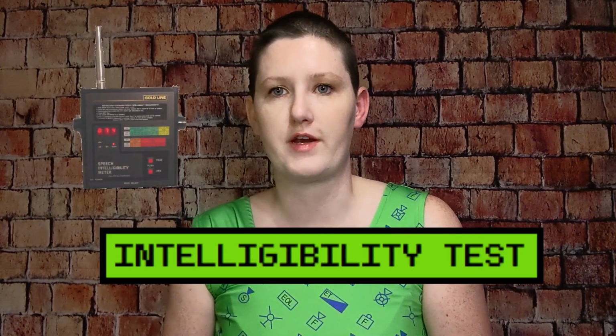Speakers are just like any other speaker, but they have more strict requirements on functionality and intelligibility. Often jurisdictions will require an intelligibility test, during which a tone-generating device is connected to the input of the EVAC panel or mass notification panel. The inspector will walk around the building with a device with a microphone that compares the sound coming from the building's speakers to the sound that the tone generator is creating to make sure that they match up. If the test goes well, this is a pretty good indication that when the verbal message is played, it will be clearly intelligible or understandable to the building occupants when the alarm is activated.